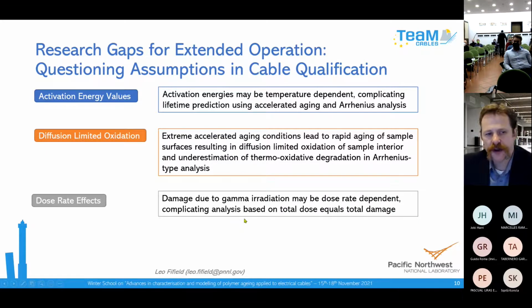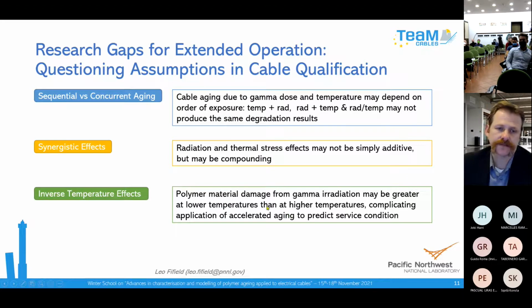Okay, next assumption is dose rate effects. Like I mentioned, if 50 megarads, or 500 kilogray, were assumed as the dose over 40 years during qualification, that was often applied all at once at a high rate, like 1,000 gray per hour or more. And the question is, when you apply a total dose over a few hours versus over a low dose rate, maybe 10 gray per hour or 1 gray per hour over many years, do you get the same degradation mechanism? So that's a dose rate effect.